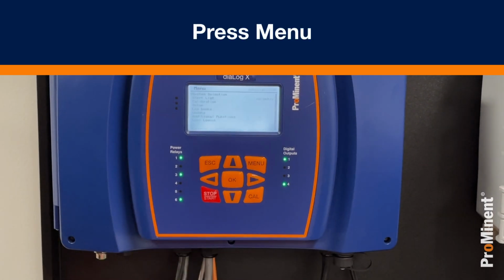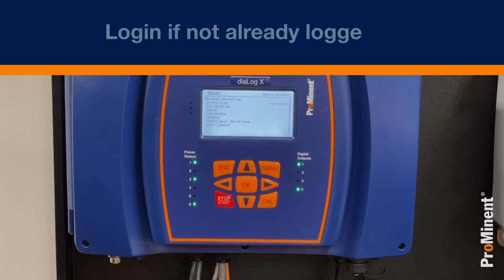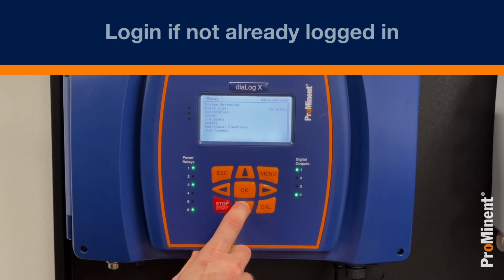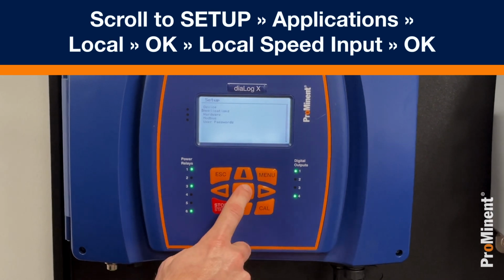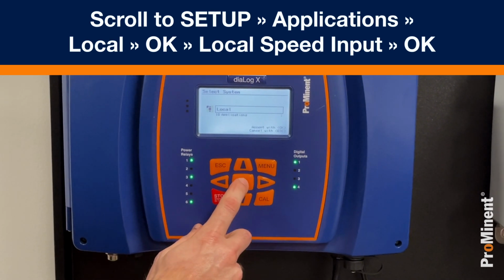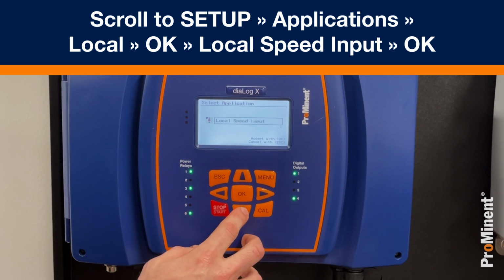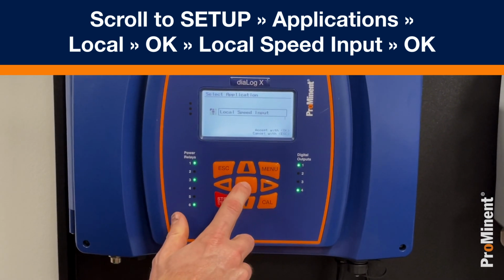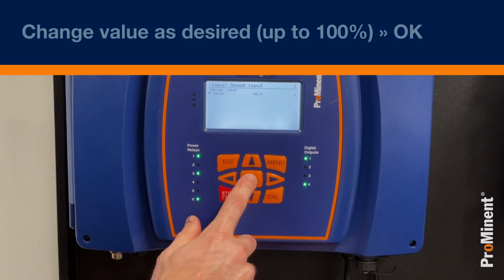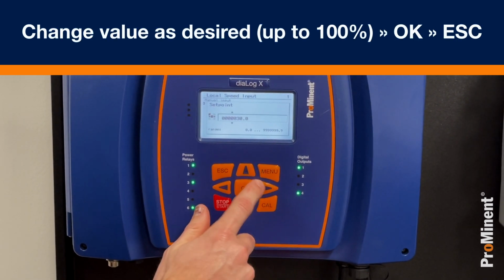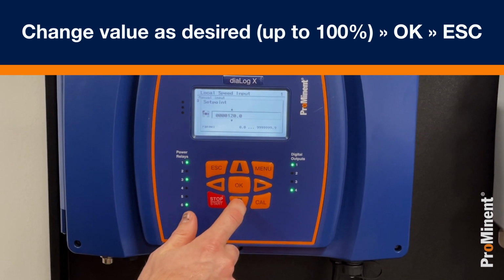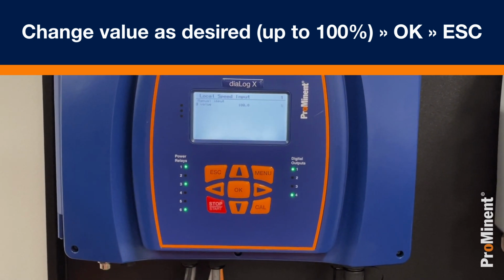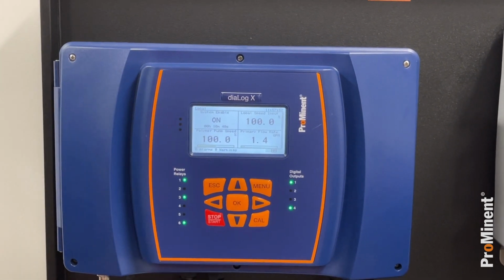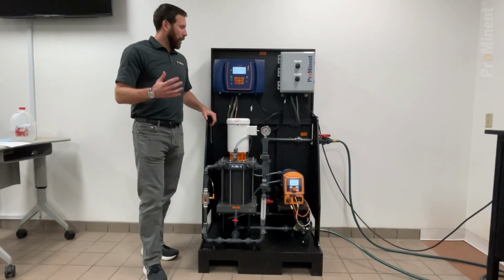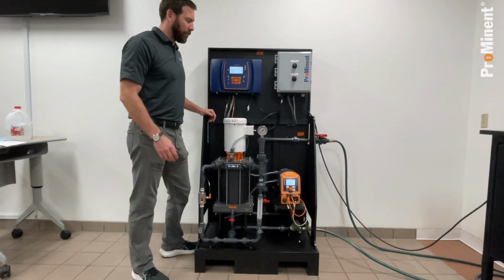To do that, I'm going to hit the menu key. I'm already logged in. If you're not, you need to log in. We already are. So I'm going to go to Setup, Applications. I want to do my local system. And we're going to go to our local speed input. I'm going to hit OK. Change my value to 100%. Hit OK. And then just exit all the way out. Now my polymer pump should be running at full speed. So we increased our pump speed. Our pump's running at full speed right now.